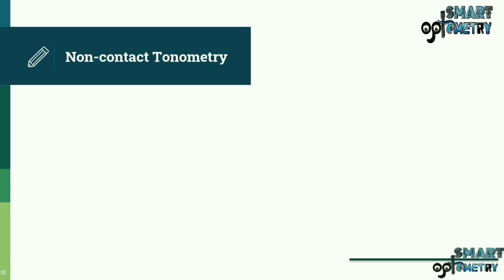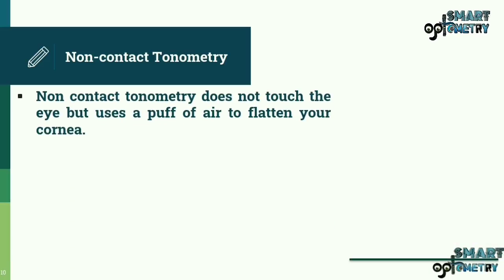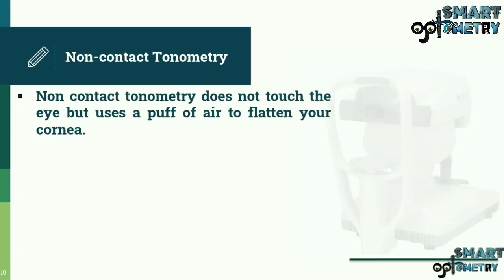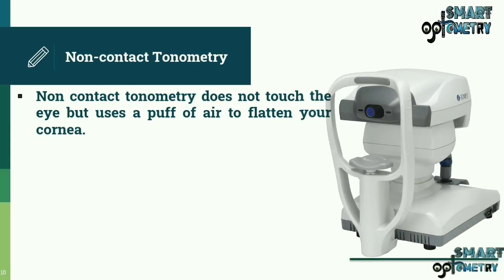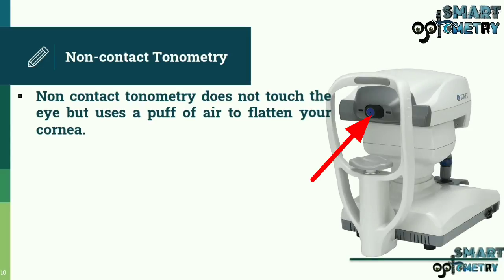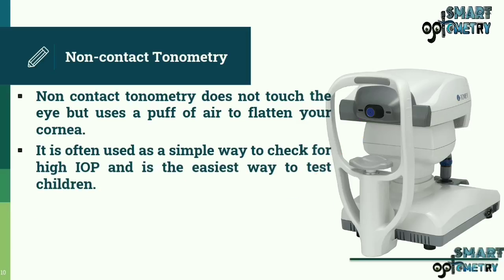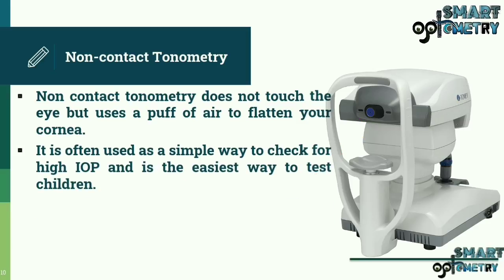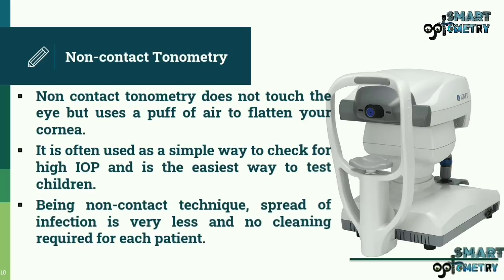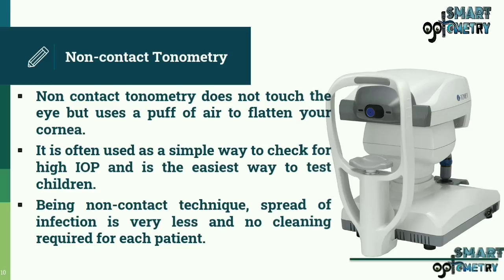Non-Contact Tonometry does not touch the eye but uses a puff of air to flatten the cornea. It is often used as a simple way to check for high IOP and is the easiest way to test children. Being a non-contact technique, the spread of infection is very low and no cleaning is required for each patient.